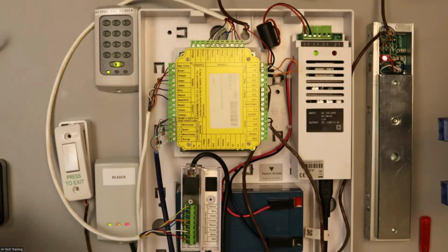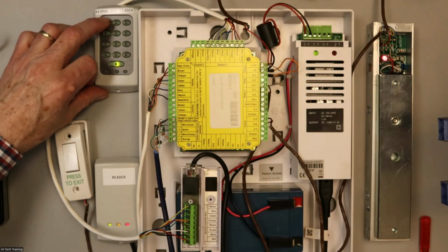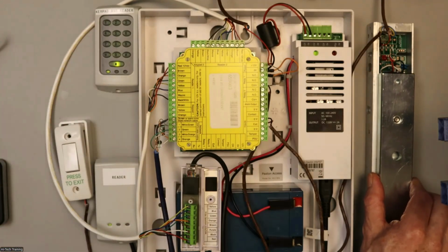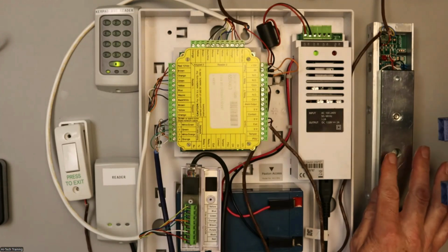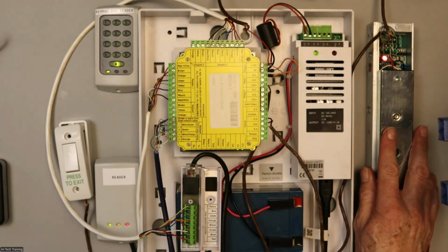So I'm going to come along with my fob first. Okay, so that's that. And my pin I'm using is 11111111, and that should open the door here for me, which it does. Stays open for the door open time, which is 8 seconds. Okay, you've got to mind yourself with these here. Don't put your finger between two items here, or you can hurt your finger a lot.